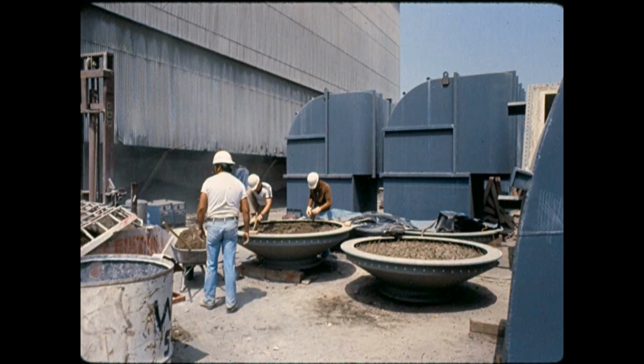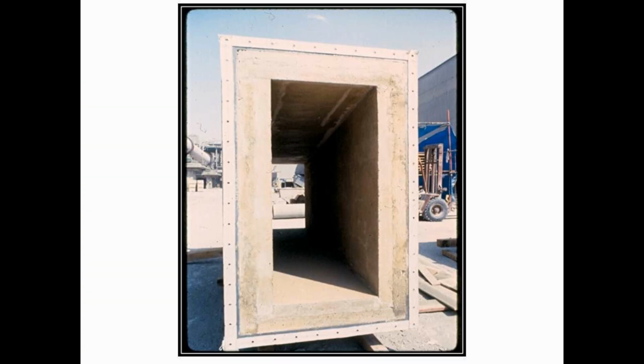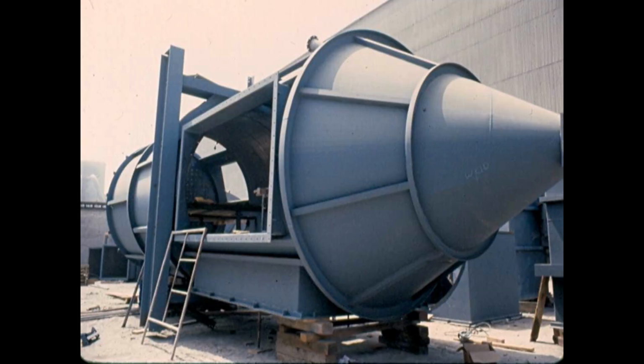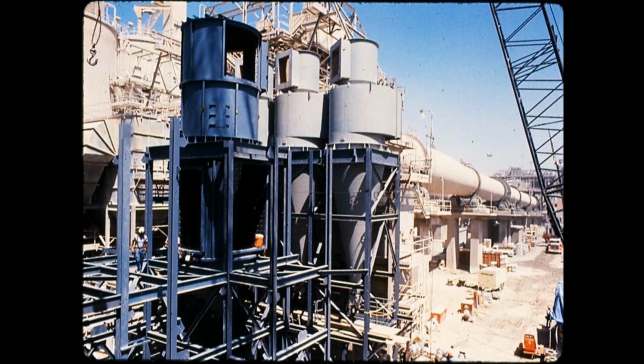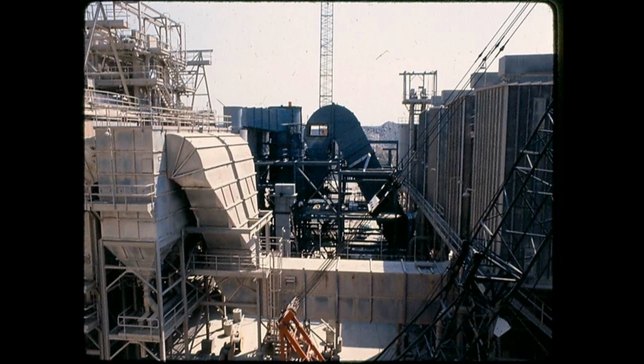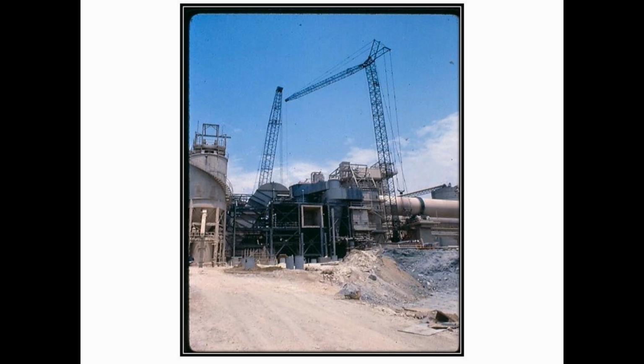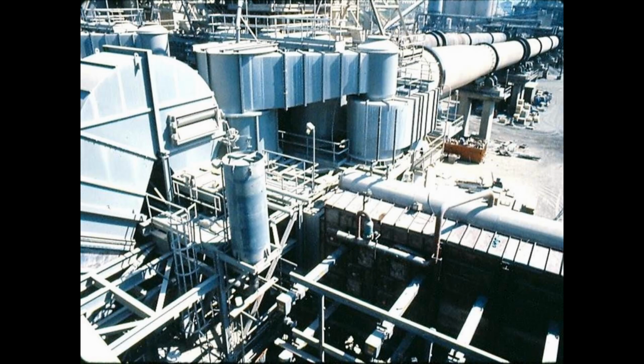In the cogeneration mode, the addition of cooling air is discontinued and the now hot combustion products are diverted through the waste heat boiler. Because kiln exhaust gases leaving the kiln will no longer be cooled with air, gas temperature will increase to approximately 1200 degrees Fahrenheit. For this reason, it was necessary to replace the existing multi-clone dust separators at the kiln discharge with new refractory-lined cyclonic separators. The new cyclonic separators remove up to 70% of the dust, which is then recycled to the kiln through a conveyor transport system.